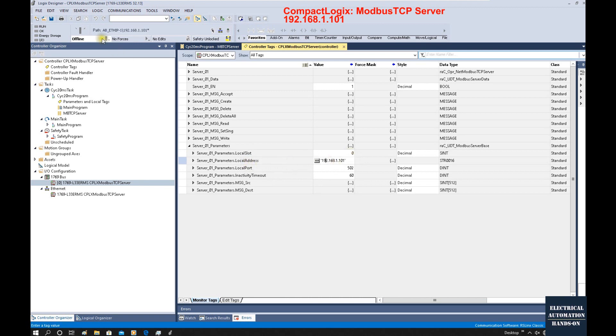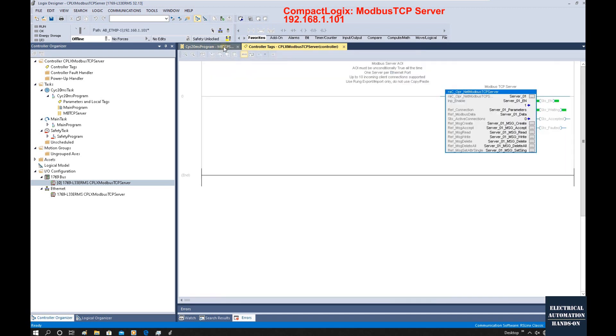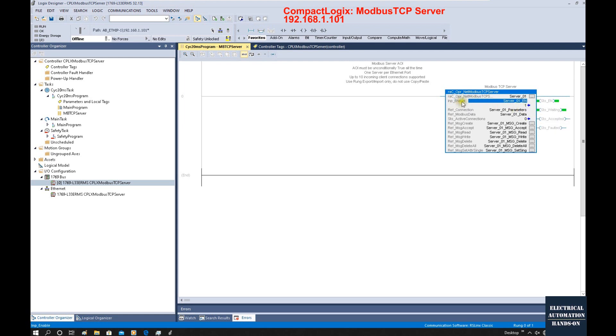The local address — this controller's IP address — is 192.168.1.101. Running as a server, the local port is 502. The timeout is 60 seconds. These are the key parameters for running as a server. Go back to this function block. Keep in mind, we need to enable the application, and we need to enable the Modbus TCP server by setting it to 1. To check the status, we can look at the active connections. Once this connection changes from 0 to 1, that means the Modbus TCP connection is established.